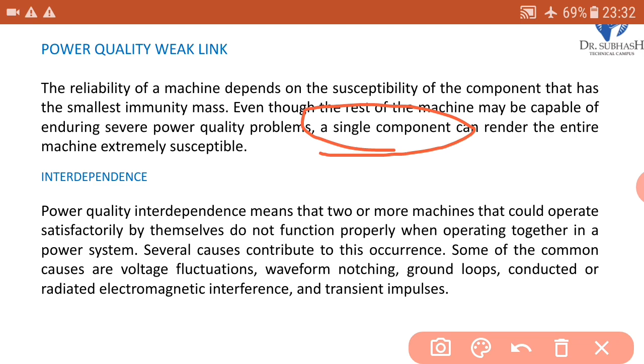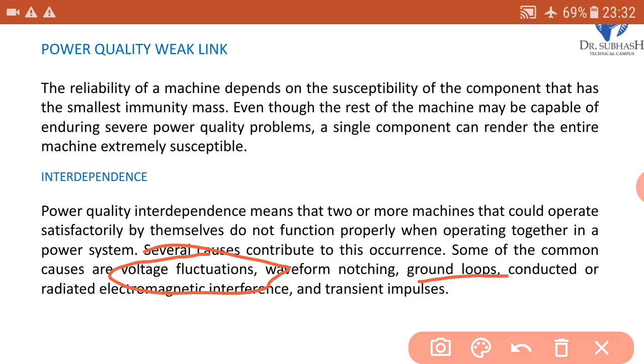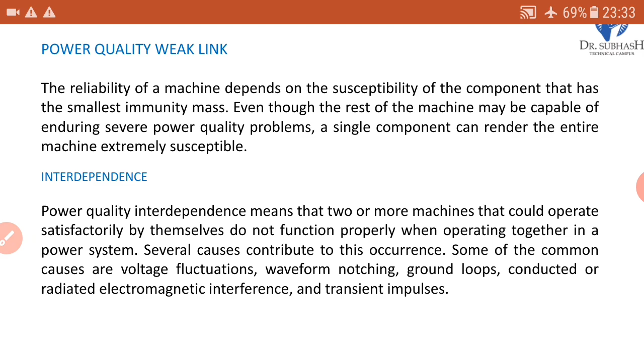Now interdependence. Power quality interdependence means that two or more machines that could operate satisfactorily by themselves do not function properly when operating together in a power system. Several causes contribute to this occurrence. Some of the common causes are voltage fluctuations, waveform notching, ground loops, conducted or radiated electromagnetic interference, and transient impulses. So these are the cases where one event can affect neighboring equipment.